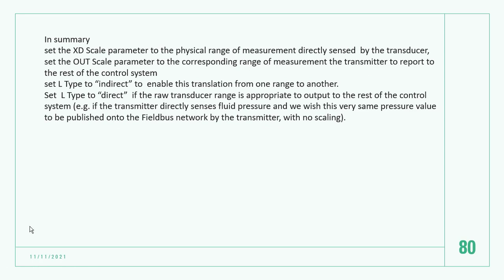Set the XD scale parameter to the physical range of measurement directly sensed by the transducer. Set the out scale parameter to the corresponding range of measurement the transmitter is to report to the rest of the control system. Set L type to indirect to enable this translation from one range to another. Set L type to direct if the raw transducer range is appropriate to output to the rest of the control system. For example, if the transmitter directly senses a pressure and we wish this very same pressure value to be published onto the Fieldbus network, with no scaling, we use direct.